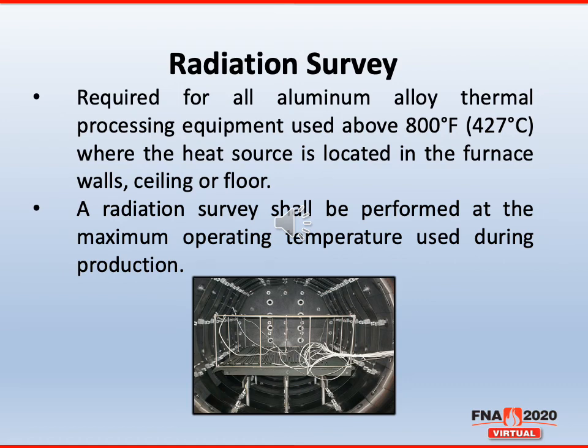So the change for the radiation test survey: prior to the release of the specifications in AMS 2750E and before, it only required that the radiation test surveys be performed on all solution heat treating of aluminum alloys. And the wording has changed. Now it's required for all aluminum alloy thermal processing used above 800 degrees, where the heat source is located in the furnace walls, ceiling, or floor. In other words, those suppliers that would have a vacuum aluminum braze furnace, for instance, now will require a radiation test survey on those furnaces. And those radiation surveys shall be performed at the maximum operating temperature used during production.